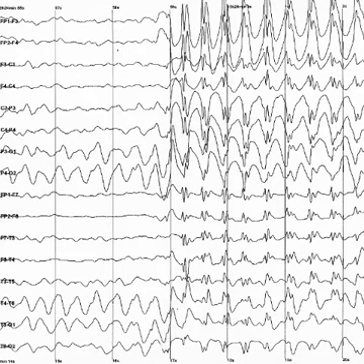The most prominent eye induced artifacts are caused by the potential difference between the cornea and retina, which is quite large compared to cerebral potentials. When the eyes and eyelids are completely still, this corneo-retinal dipole does not affect EEG. However, blinks occur several times per minute, the eyes movements occur several times per second. Eyelid movements, occurring mostly during blinking or vertical eye movements, elicit a large potential seen mostly in the difference between the electrooculography channels above and below the eyes. An established explanation of this potential regards the eyelids as sliding electrodes that short-circuit the positively charged cornea to the extra-ocular skin. Rotation of the eyeballs, and consequently of the corneo-retinal dipole, increases the potential in electrodes towards which the eyes are rotated, and decrease the potentials in the opposing electrodes.